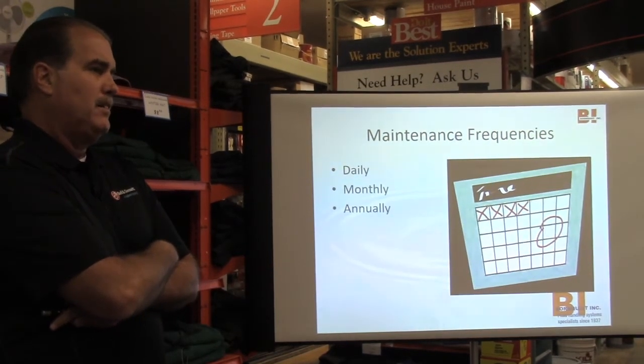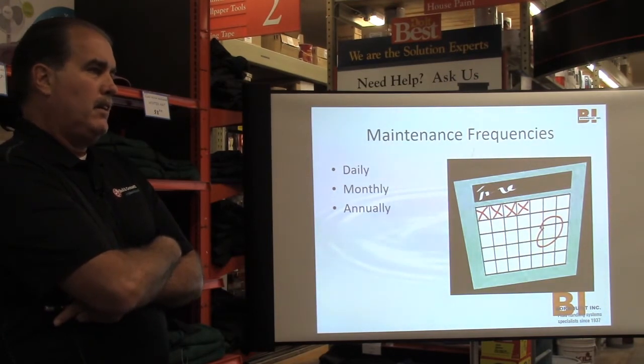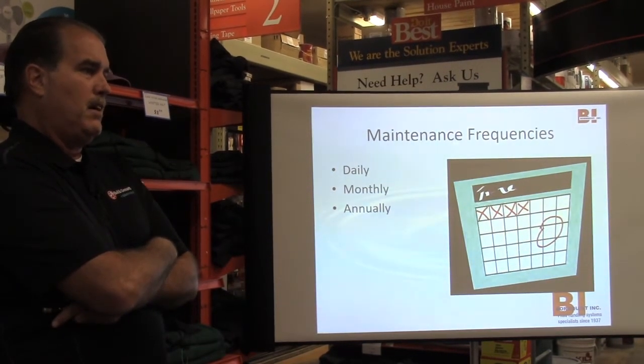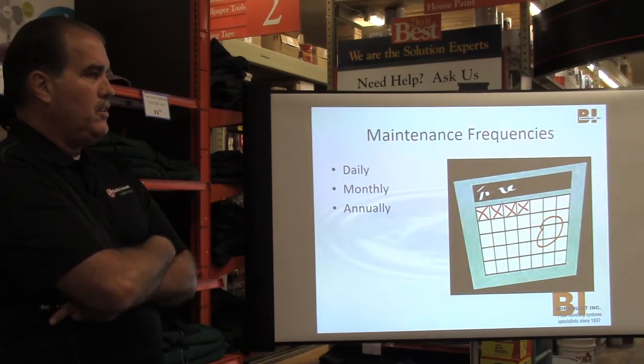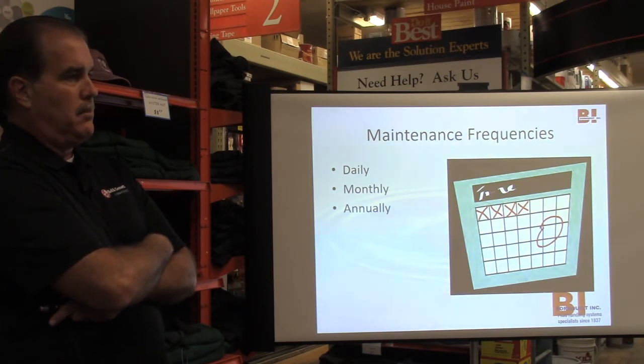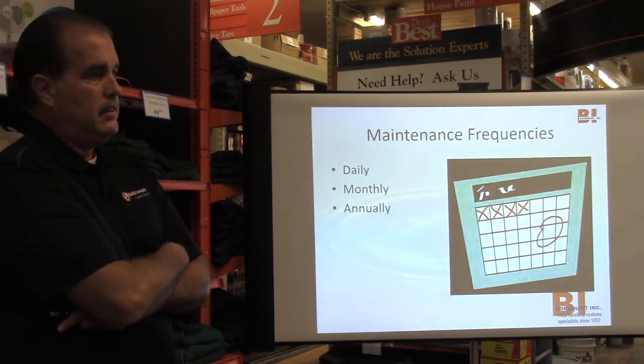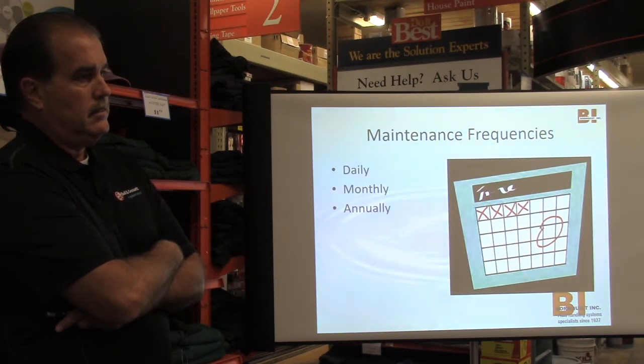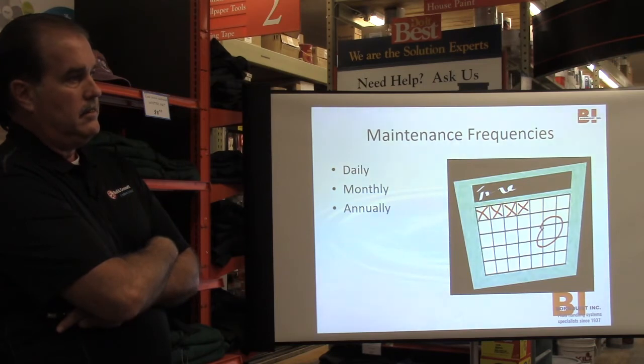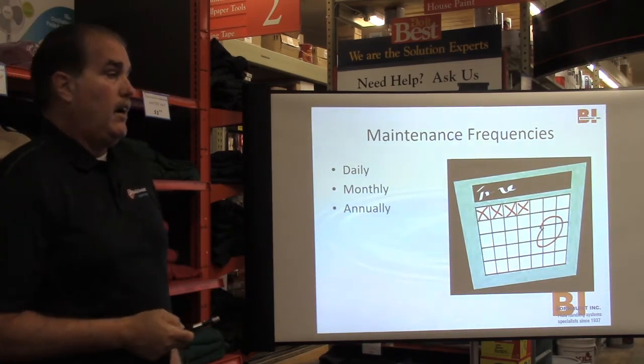Banging is usually water hammer, typically. But it could be metal expansion as well, making a ticking noise or whatever. But if it's banging, that's usually something water-locked somewhere that's not getting back. Is it possibly in the pitch of the return pipes? How long does it last? It depends on how much the boiler is firing up, depending on the weather. It can be like 4 or 5 really loud knocks over the course of maybe 5-10 minutes. It doesn't do it constantly.